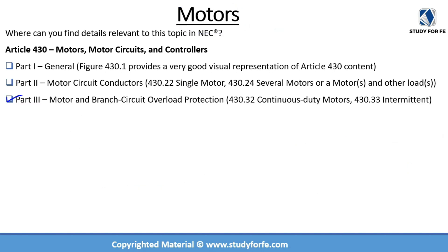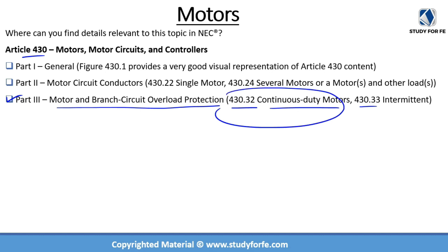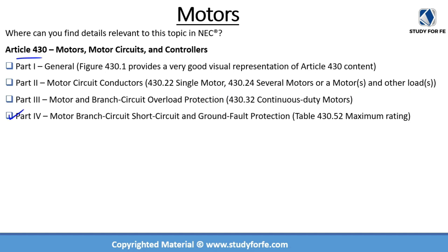Part 3 of Article 430 is titled Motor and Branch Circuit Overload Protection. I would like to draw your attention to two sections: 430.32, which deals with continuous duty motors, and 430.33, which deals with intermittent duty. Most of the time we are dealing with continuous duty motor applications, so please pay special attention to 430.32. Section 430.33 is very brief, so it will be a quick read.